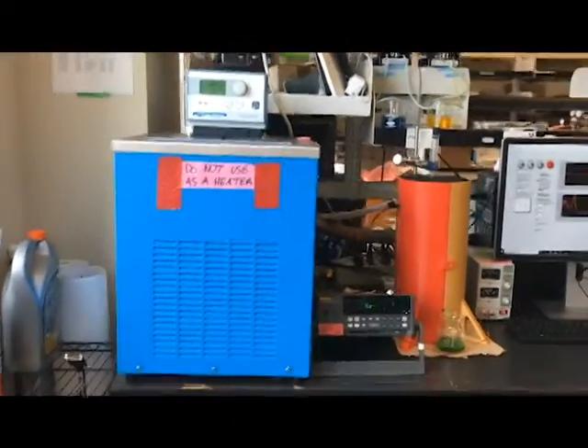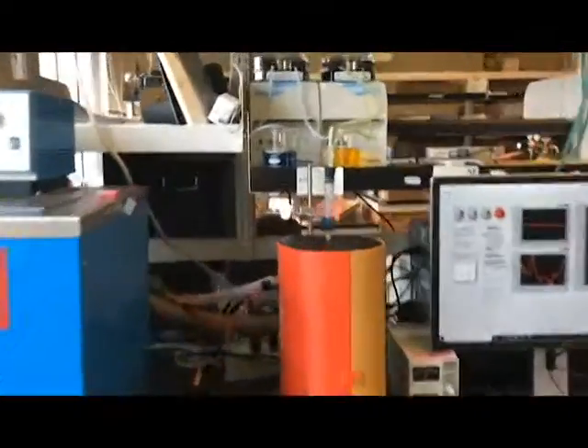As you can see, we have the chiller on the left here that is used to cool the refrigeration fluid that runs through the outlet tube at the back of the chiller. The outlet tube goes to the heat tape that is used to heat the chiller fluid until it reaches the desired temperature and then flows through the housing unit.